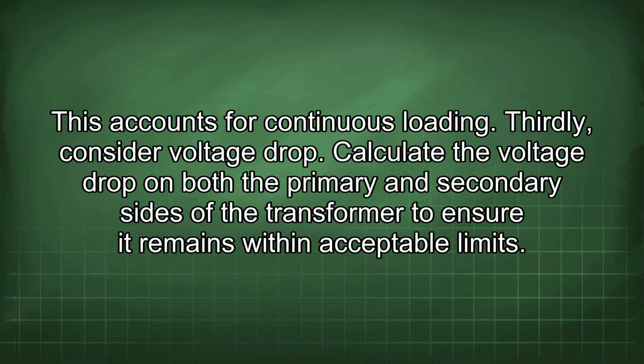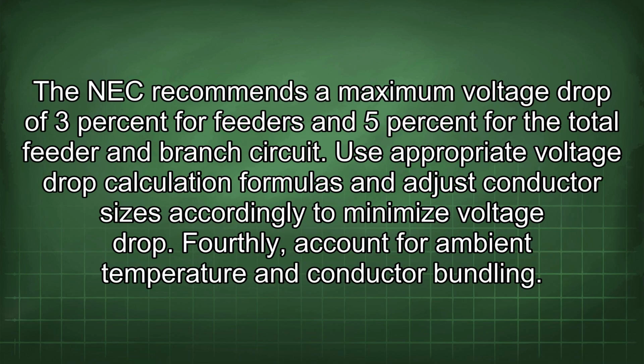Thirdly, consider voltage drop. Calculate the voltage drop on both the primary and secondary sides of the transformer to ensure it remains within acceptable limits. The NEC recommends a maximum voltage drop of 3% for feeders and 5% for the total feeder and branch circuit. Use appropriate voltage drop calculation formulas and adjust conductor sizes accordingly to minimize voltage drop.